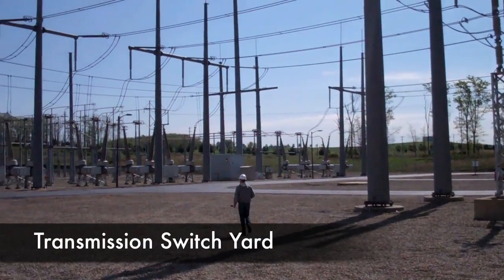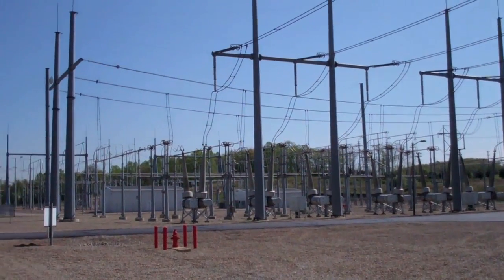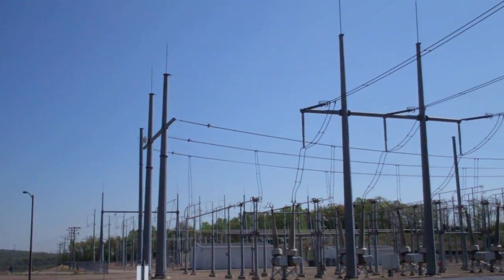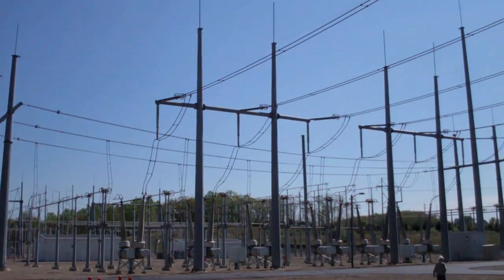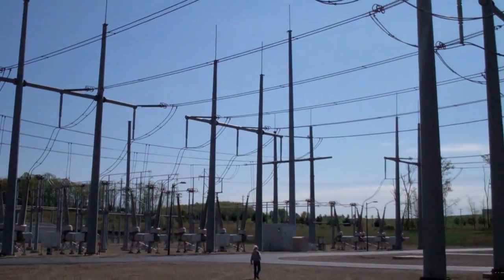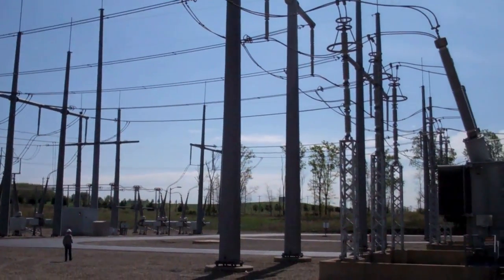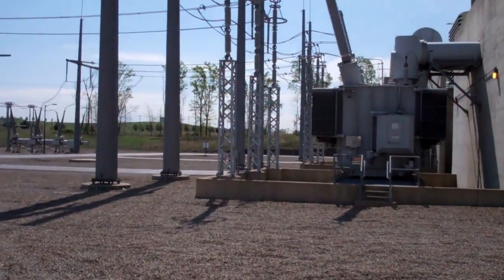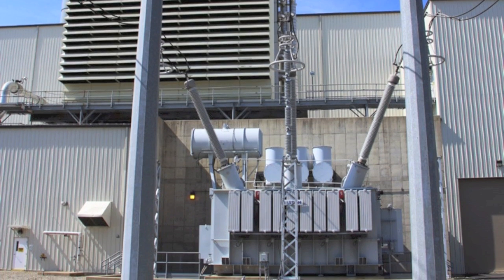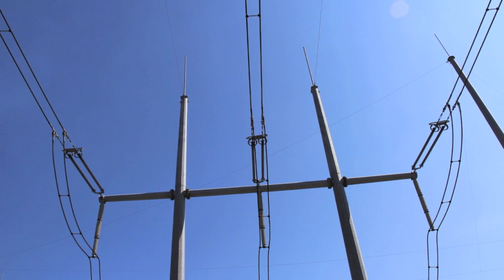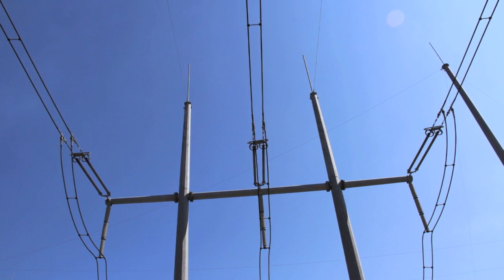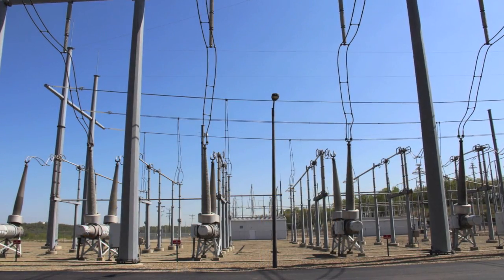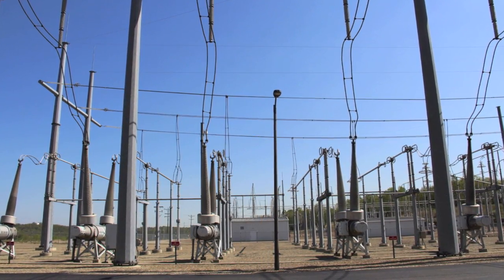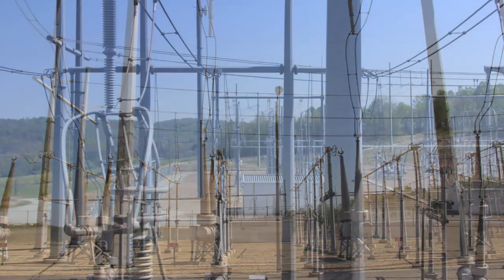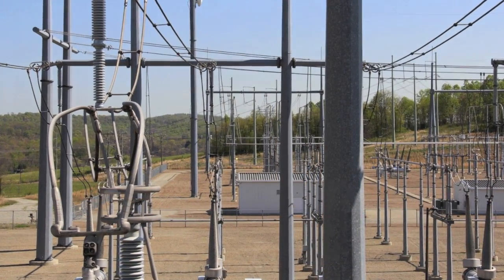This is our transmission switchyard. From here, our generators produce our electricity at 18,000 volts. These main transformers that you see here convert that 18,000 volts to 525,000 volts. And that's what we connect to the power system at, 525,000 volts. The reason we step it up to that high of a voltage is that it's more efficient for the transmission lines. So the higher your volts are, the lower your current is, so you have less thermal loss in the transmission line. We produce 620 megawatts is what our nominal rating is. 620 megawatts would power about 500,000 normal homes.